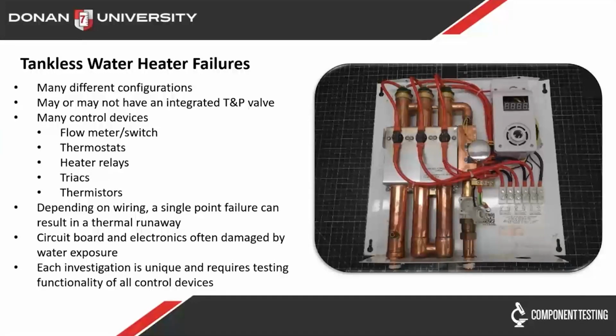And all the while, these hot water heaters are monitoring the inlet and outlet temperatures, they're monitoring the flow sensors. And kind of what I've seen on these is that depending on how they're constructed, depending on the devices that are on board, there are multiple devices that can fail, and a single point failure mode, meaning if one of these devices fails, it can result in a thermal runaway. A thermal runaway is when the heat does not turn off when it should. So either when the water has stopped flowing, when you've stopped calling for water, or when there's been a blockage of some sort and the water heater should turn off but doesn't.